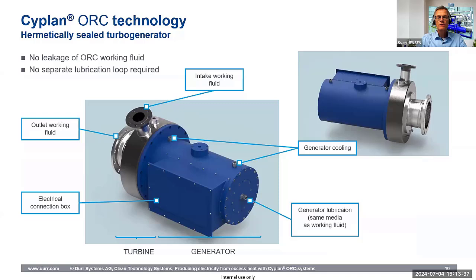These are 2 pictures of our turbo generator. We have a completely encapsulated system—the turbine, in the silvery part, and the turbo generator, in the blue part, are enclosed in one common casing. So we have one shaft, one common casing, and that's important because this ensures a completely tight system. We call it the hermetically sealed generator. We work with natural ORC, natural hydrocarbons, and for that reason it's really important that we keep that working media inside our system. The entire system, as we saw in the earlier picture, is classified as a technically tight system.